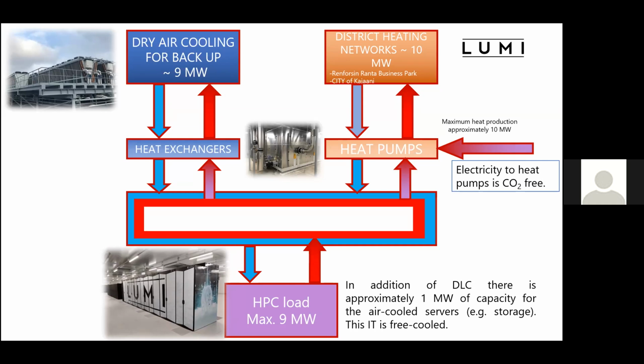This shows the basic principle of how we do our cooling for the HPC DLC load, and approximately 9 megawatts will be HPC load on the Lumi data center. Then we are using heat pumps, and the heat pump evaporators will raise the outlet water from Lumi to 80 Celsius degrees to get it suitable for district heating.